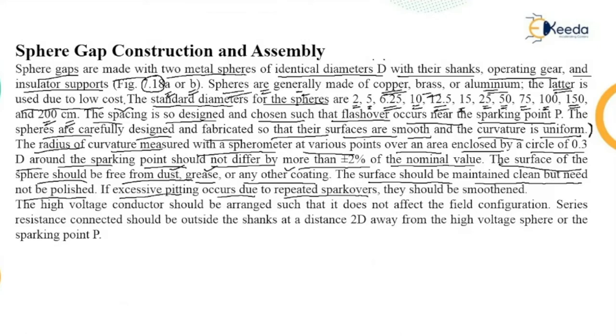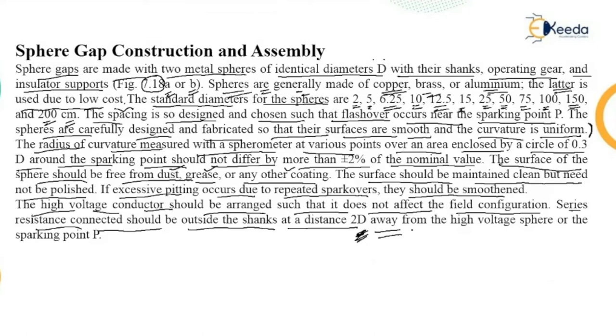The surface should be maintained clean but need not be polished. If excessive pitting occurs due to repeated spark overs, it should be smoothed. The high voltage conductor should be arranged such that it does not affect the field configuration. The series resistance connected should be at a distance of at least twice D — the diameter of the sphere — from the high voltage sphere or the sparking point P.